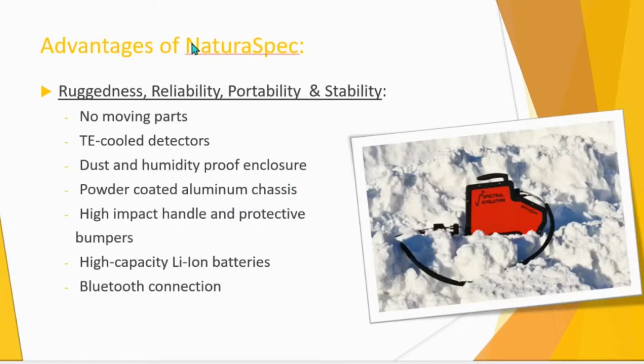So as far as the ruggedness, the reliability, portability, stability of the instrument, our technology is based on solid state detectors. What that means is that those detectors have no moving parts. So whether it's in the optical path or in the electronic box, there are no moving parts in our instruments, unlike many other spectrometers that have moving gratings. No moving parts mean no motors, no parts that can come loose. So we have a very stable and fixed optical path and electronic system, which is of great advantage to survive under shock and vibrations that may occur in the field. So the reliability of our instrument is very high from that standpoint of being rugged.